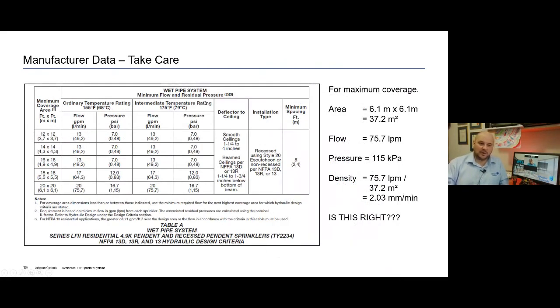So what a lot of people will do is say, right, I've got an area 6.1 by 6.1. That's 37.2 square meters. My flow from my data sheet is 75.7 liters at 115 kilopascals, which gives me a density of 2.03 millimeters per minute.